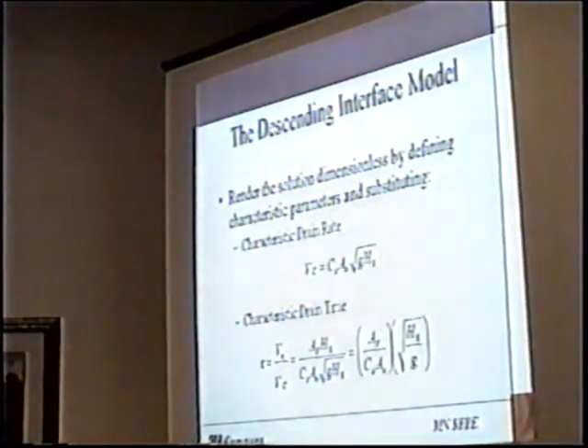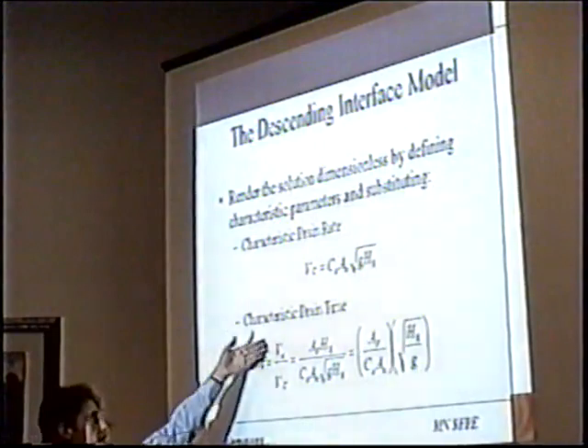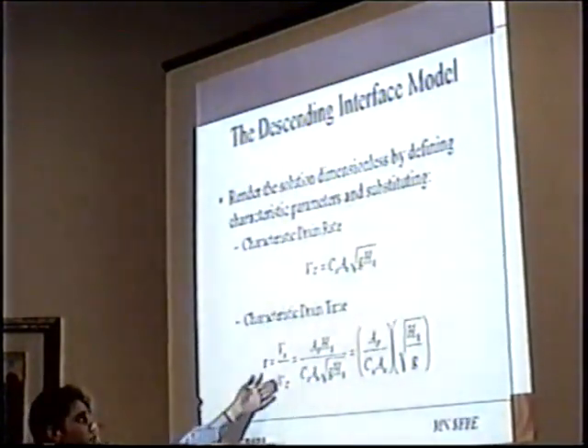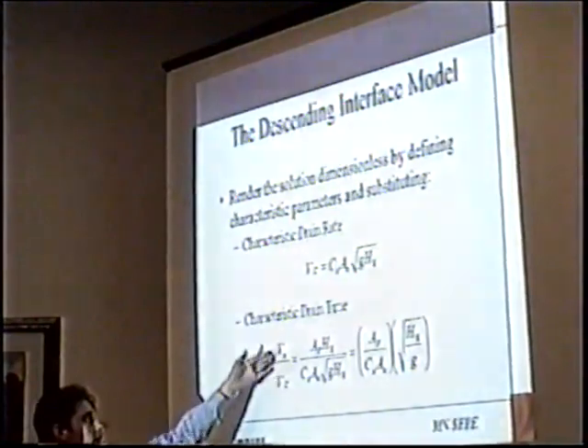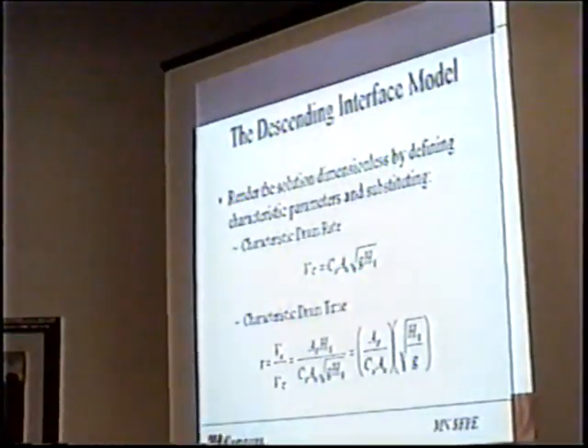So we go ahead and we introduce some characteristic quantities. We'll start with a characteristic drain rate. This is essentially just taking our regular gas flow through this equation and assuming that the driving force of the pressure differential is equal to a full enclosure worth of agent. And it results down to this. That way we can say, well, let's assume that the fastest force pushing agent out of the room would be if we assume it never leaves, and it's just that initial criterion. And then our characteristic drain time is going to be the entire volume of the enclosure divided by our characteristic drain rate. The volume cancels, we get units of seconds, and that would be our characteristic time.